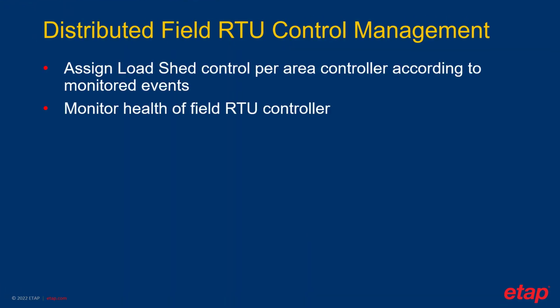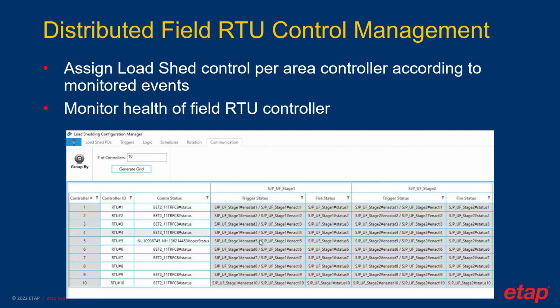Part of the requirements of a distribution load shedding system is that it is required to provide fast coordinated response over large distribution areas. The eTAP iDLS controller can be programmed to communicate to multiple RTUs, which are going to be the substation devices executing the load shedding. As part of the configuration, the system will need to consider what RTUs will participate in the monitoring and load shed control for each contingency event. This is necessary as some of the events may be localized just for a single substation or substations and not global for the entire network, such as a feeder overload.